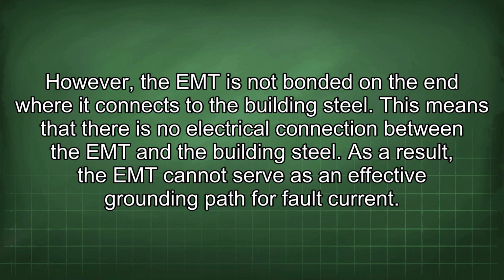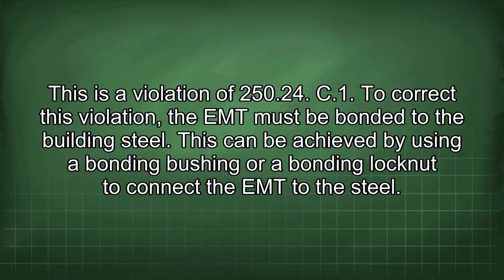However, the EMT is not bonded at the end where it connects to the building steel. This means that there is no electrical connection between the EMT and the building steel. As a result, the EMT cannot serve as an effective grounding path for fault current. This is a violation of 250.24 C1. To correct this violation, the EMT must be bonded to the building steel.